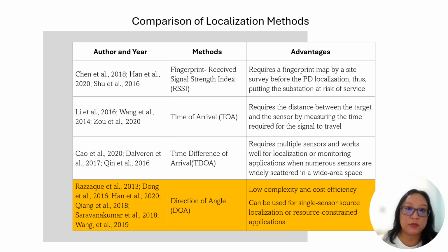When we use this method, it requires a fingerprint map from a site survey before we do the partial discharge localization, putting this substation at risk of service. We need to shut down the substation in order to survey the site for the fingerprint map.